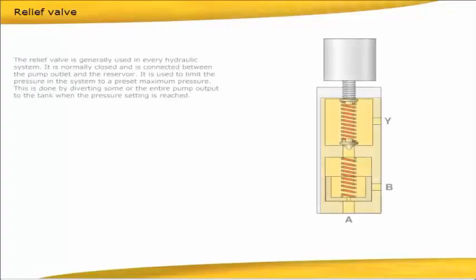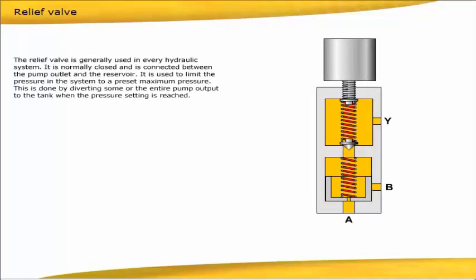The relief valve is generally used in every hydraulic system. It is normally closed and is connected between the pump outlet and the reservoir. It is used to limit the pressure in the system to a preset maximum pressure. This is done by diverting some or the entire pump output to the tank when the pressure setting is reached.